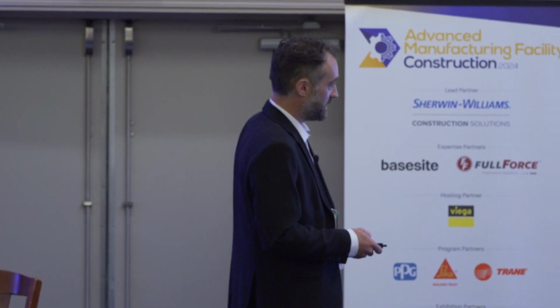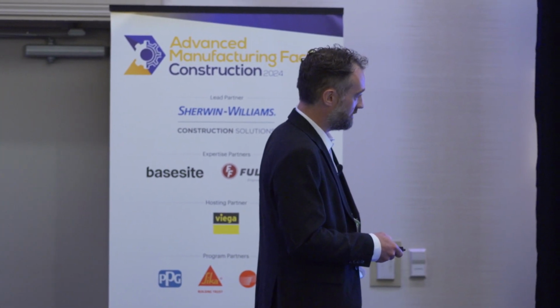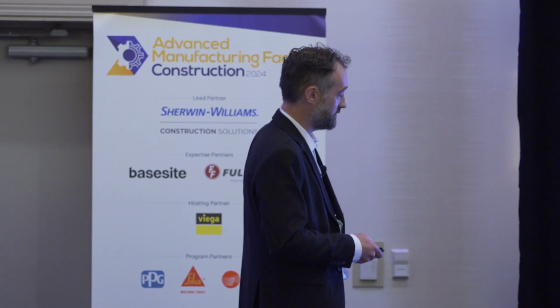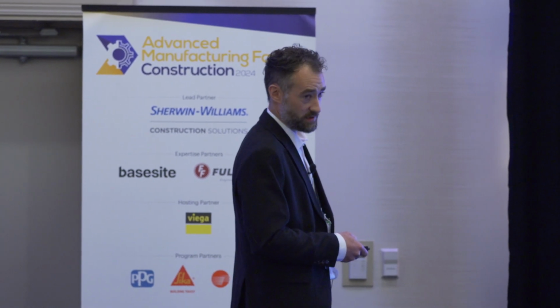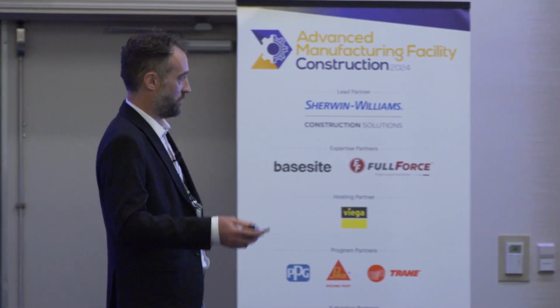Here's a little cutaway section of a fab, very simple. All your process tools are in here. You've got all your sub-fab utilities in here, so all these pipes running horizontally provide all the process mechanical and gas utilities to the tools. Underneath, we've got the electrical distribution system, and we've got chemical and gas distribution cabinets in there as well. So this is what we call the layout dependent scope, or the sub-fab fit out.